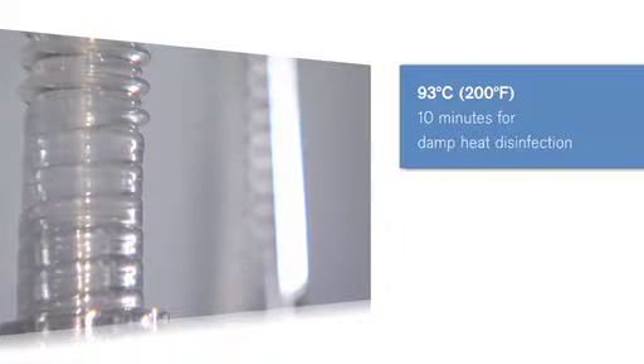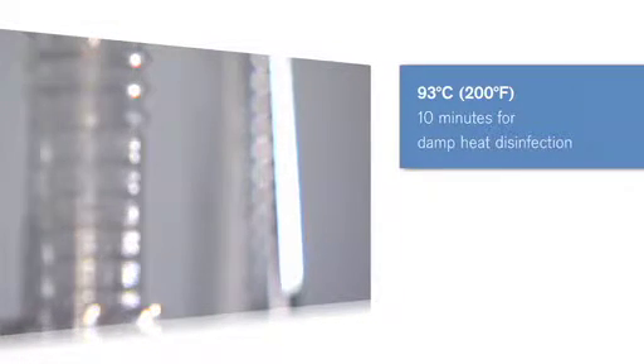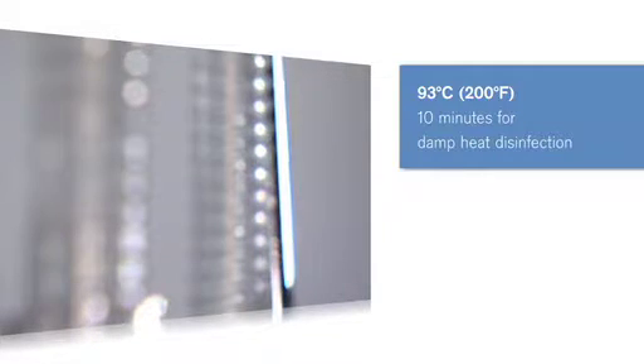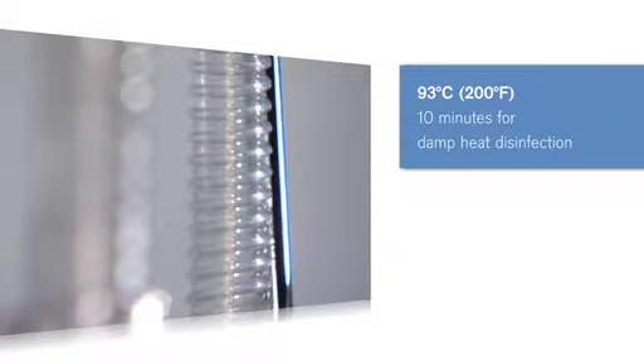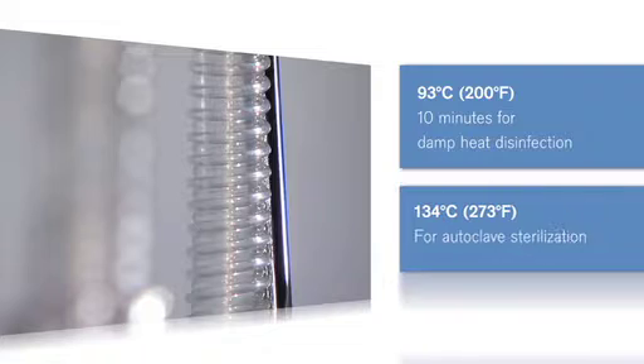Only reusable ventilation hoses should be sterilized. Use detergent in the cleaning disinfection machine. 93 degrees Celsius or 200 degrees Fahrenheit, 10 minutes for damp heat disinfection. 134 degrees Celsius or 273 degrees Fahrenheit for autoclave sterilization.